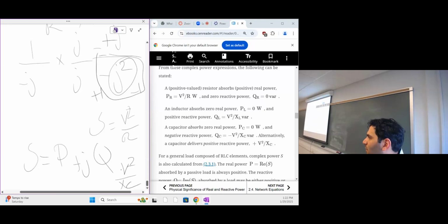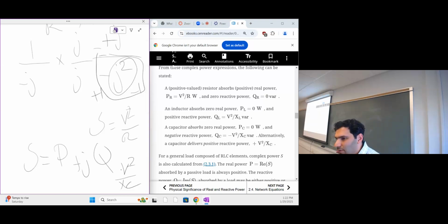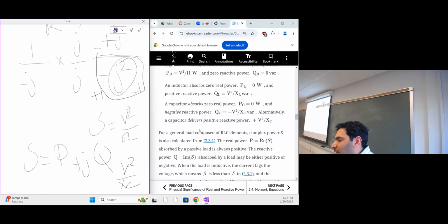So now we understand why we really need those reactive devices for power flow. Whenever a voltage drop happens, a typical solution is to put a capacitor bank on the transmission line at a certain level, so it starts pumping that V squared over XC to restore the voltage to its needed level, typically 110 if you are at a distribution level.